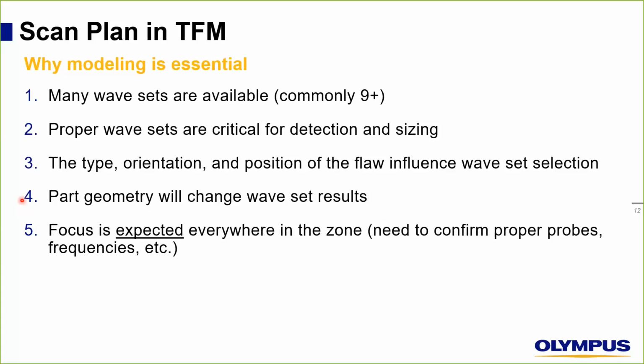Because many wave sets are available, commonly more than nine. When we talk about wave sets, we are talking about TT, TTT, etc. Proper wave sets are critical for detection and sizing. So if we don't select the right wave sets, probably we won't have good detection and, of course, good sizing. The type, the orientation and the position of the flaw influence wave set selection as well. Part geometry will change wave set results. Focus is expected everywhere in the zone, but it needs to be confirmed by using the proper probes, frequencies, etc. So modeling is really an essential tool when building a scan plan in TFM.